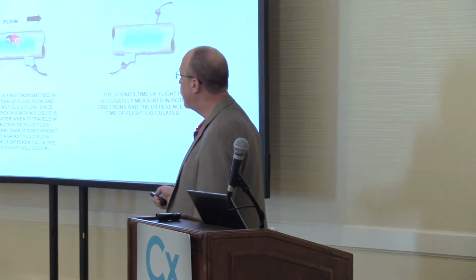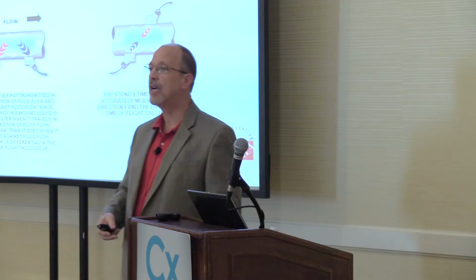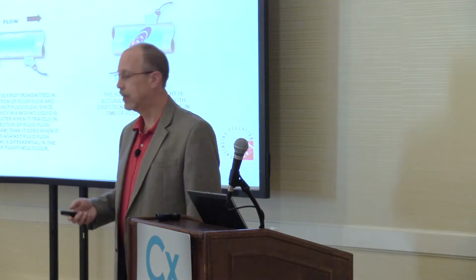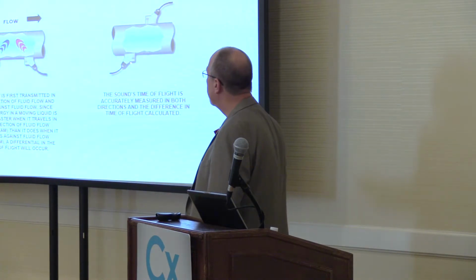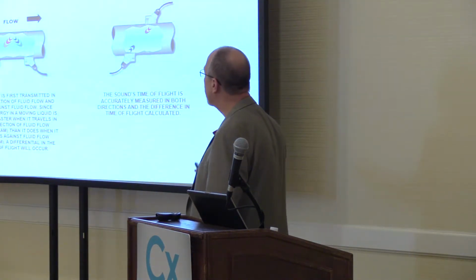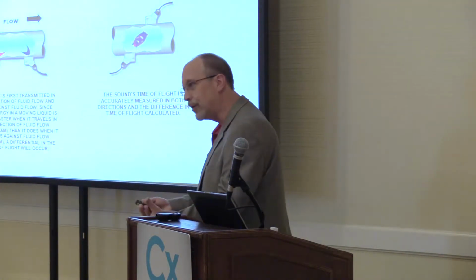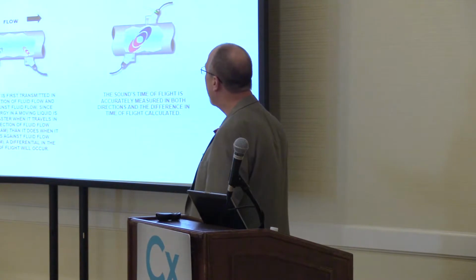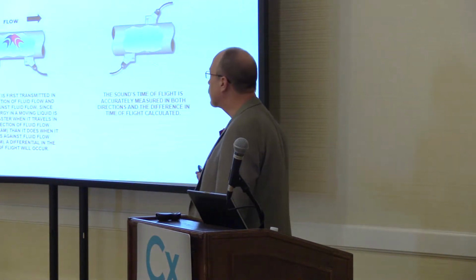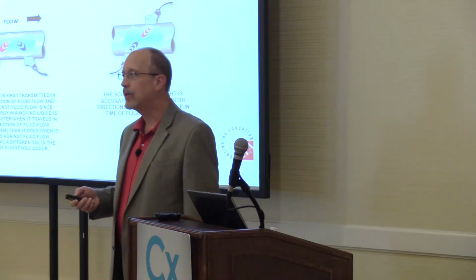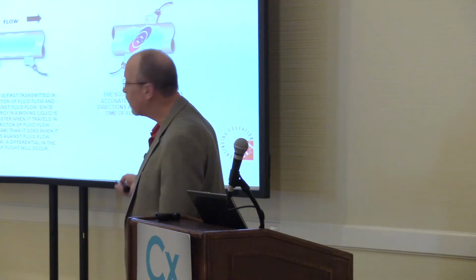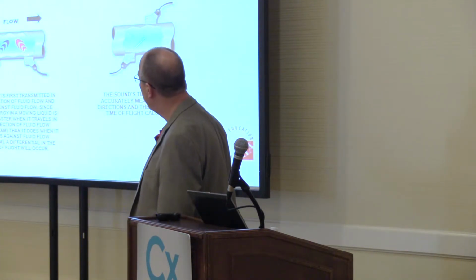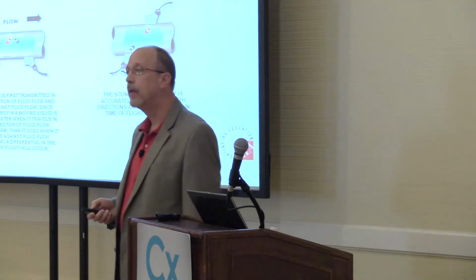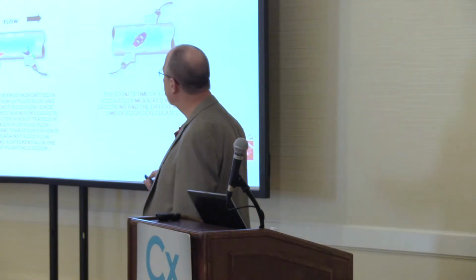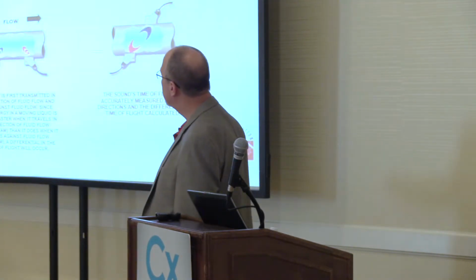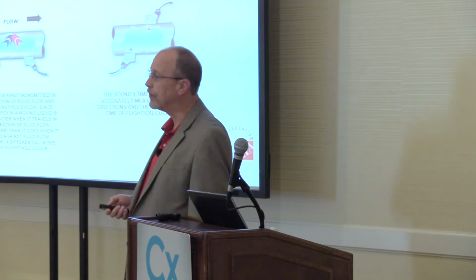Traditionally, this installation method is used for pipe sizes from about 1/2 inch up to 24 inches. This configuration here, the single path, is more powerful. It's traditionally used on very large pipe applications, 24 inches and larger, or on applications that require extra power. So if you have an application with that old 90-year-old crusty pipe that needs a little extra power because it did not work here, you might want to try this configuration because it's only got one path as opposed to the two-path configuration. So the transducer spacings are pretty much for the generic design. We'll look at frequencies later. This is the standard ultrasonic transit time transducer.